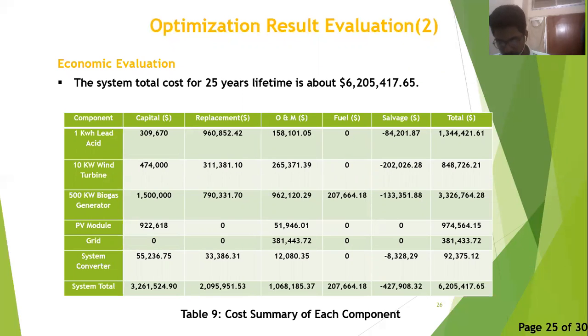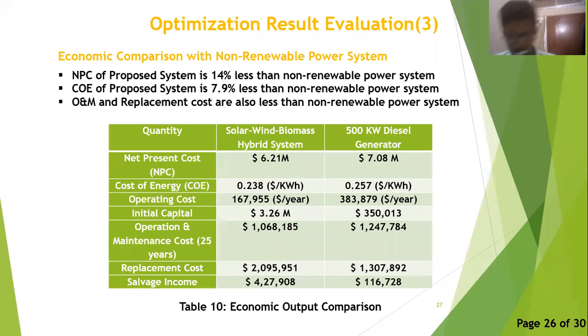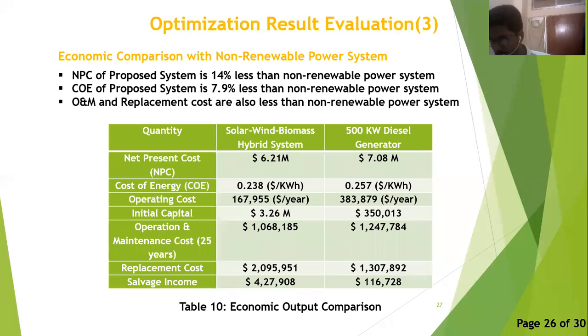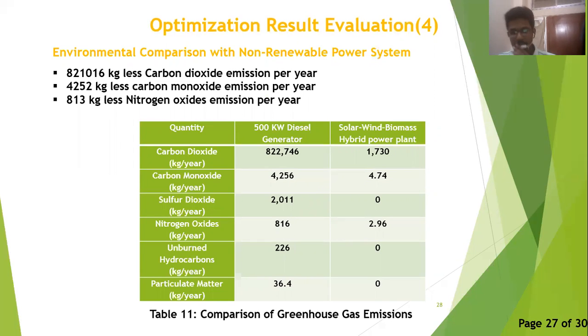We will now discuss why we should use the PV-wind biomass hybrid system instead of a non-renewable base power system. For this comparison, we consider a 500 kW diesel generator. For the same load profile, the net present cost of the hybrid system is 14% less than that of a 500 kW diesel generator. The cost of energy and operating and maintenance cost are also considerably less. The only drawback is that the initial capital investment is higher than a non-renewable power system. In terms of environmental impact, greenhouse gas emissions are much less with the hybrid system — it causes significantly less carbon dioxide, carbon monoxide, and nitrogen oxide emissions than a 500 kW diesel generator.